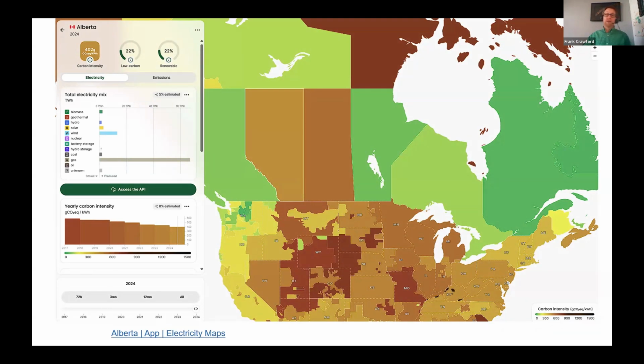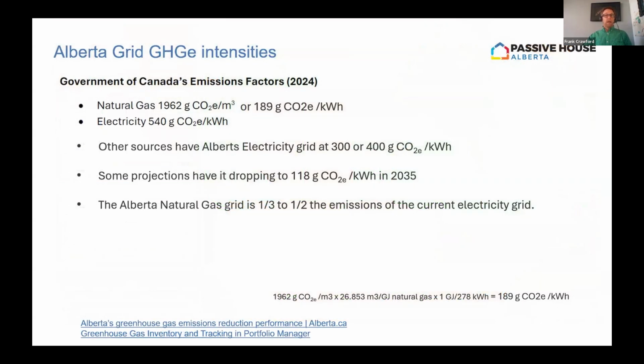And we're up to about 22% renewables, but the rest of it is now pretty much all natural gas. So unfortunately, the electrical grid grams of CO2 equivalent per kilowatt hour is anywhere between 540 and down to 300 grams, depending on which government source you look at. And the natural gas grid is 1,962 grams per meter cube. Once you convert that to kilowatt hours, it's only 189. So right now in Alberta, the natural gas grid is 1/2 to 1/3 the CO2 emissions of our electrical grid. So unless we're getting seasonal COPs of 2 or 3 or more, natural gas is a lower carbon option right now. Hopefully that will drop in the future.